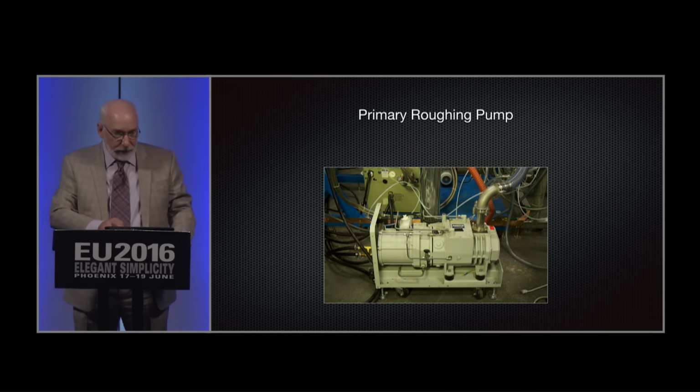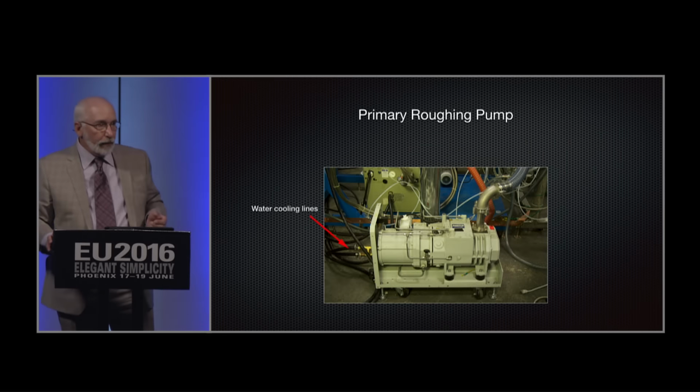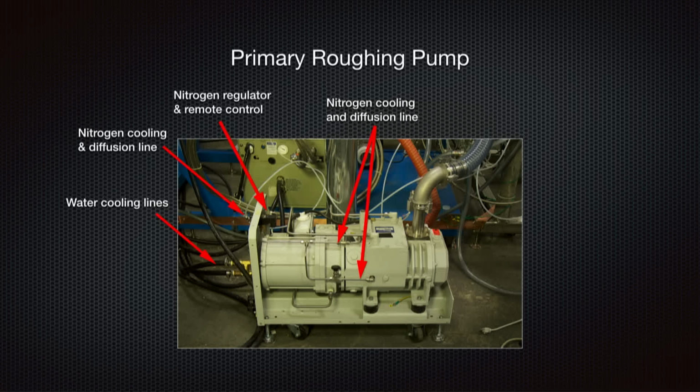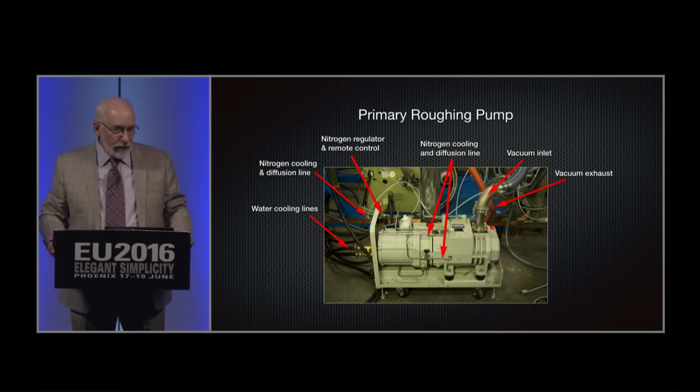So it's complex. This is the main vacuum pump, and it sucks big time. It will take the chamber down to 10 minus 2 in about 15 minutes. If anybody knows anything about vacuum pumps, this is from Oerlikon.